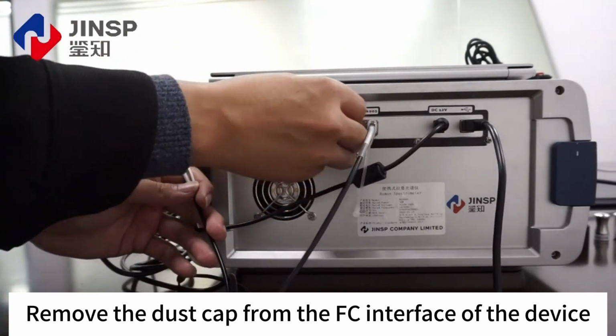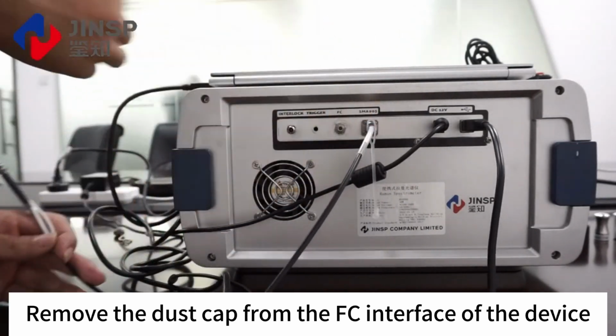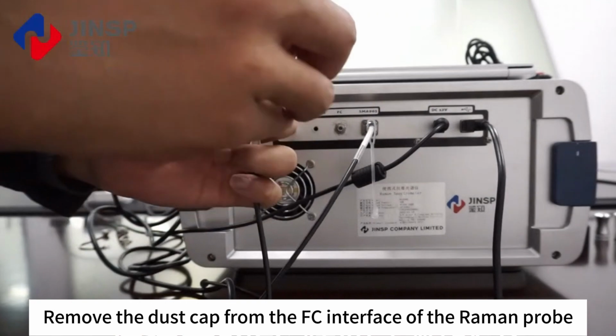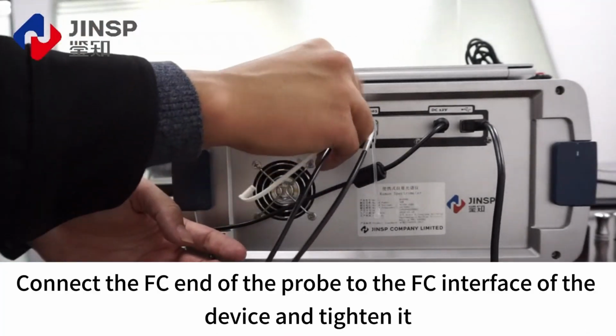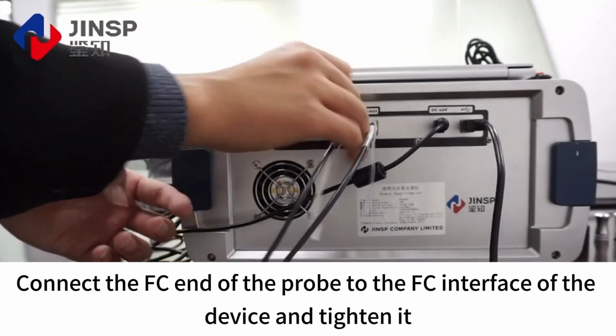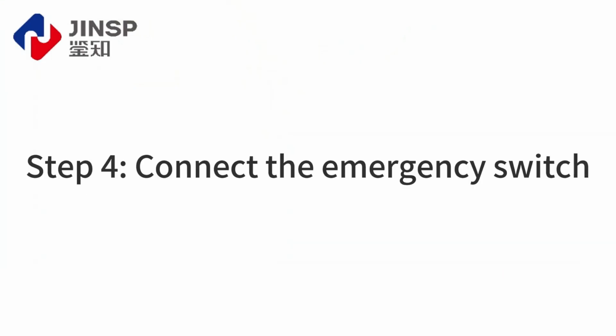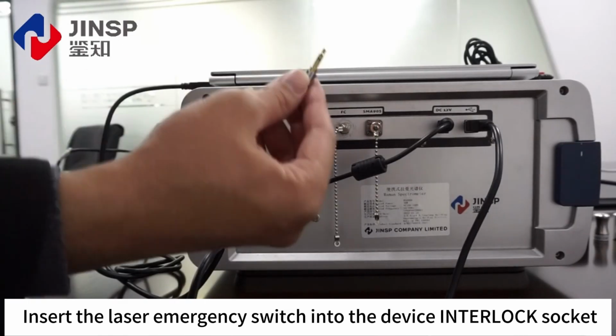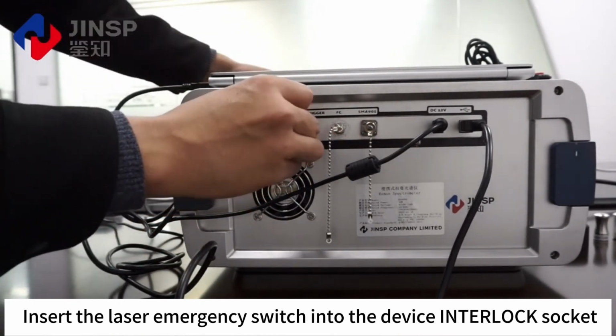Remove the dust cap from the FC interface of the device. Remove the dust cap from the FC interface of the Raman probe. Connect the FC end of the probe to the FC interface of the device and tighten it. Step 4. Connect the emergency switch. Insert the laser emergency switch into the device interlock socket.